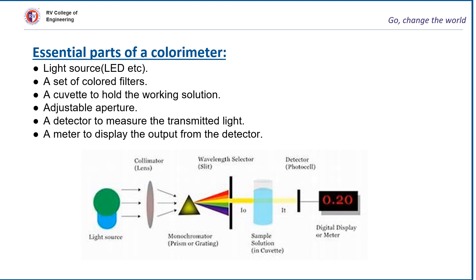First, the colorimeter is calibrated using a standard solution of known concentration. Then, a light ray of a certain wavelength is directed towards a given unknown solution. The light passes through a series of different lenses and filters. The filter allows only the required wavelength of light to pass through and reach the cuvette, where it is transmitted, reflected, and absorbed by the solution. The transmitted light falls on the detector and the output display meter shows the output from the device.